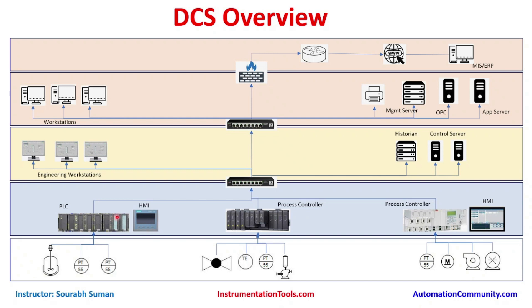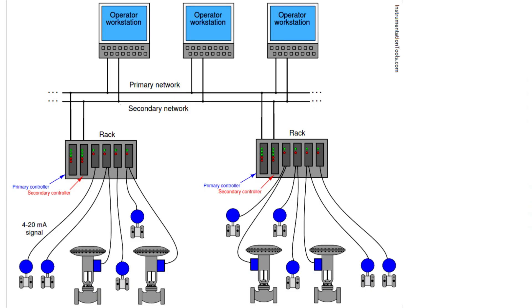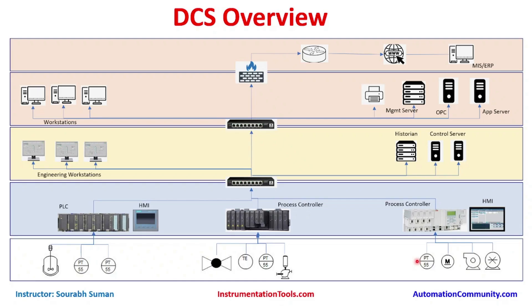In a DCS system, we have field-level instrumentation including pressure transmitters, temperature measuring instruments, level measuring instruments, and flow measuring instruments. Apart from measurement, there is also the command part — solenoid valves and motorized valves which receive commands from the DCS and process them to downstream equipment. This is the basic field level, or level zero.